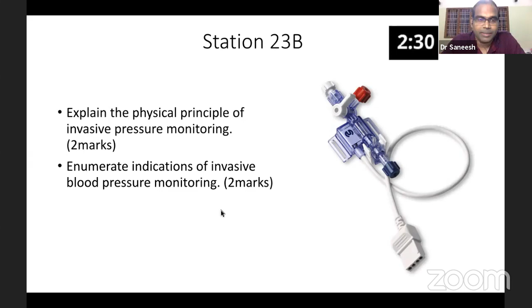Okay, the indications for invasive blood pressure monitoring. So the principle, if you can draw a diagram, that can save a lot of time: the Wheatstone bridge principle, the strain gauge principle. As the resistance changes, the resultant output current changes, and that is plotted into the graph on the electronic monitor, helped by the processor. So you will get the highest value as the systolic BP and the lowest as the diastolic BP, and you will get the mean arterial pressure also. The transducer should be located or zeroed at the level of the phlebostatic axis.